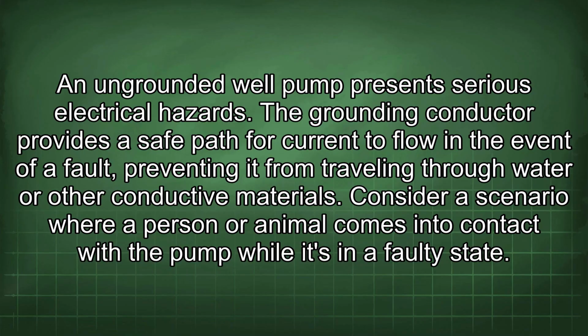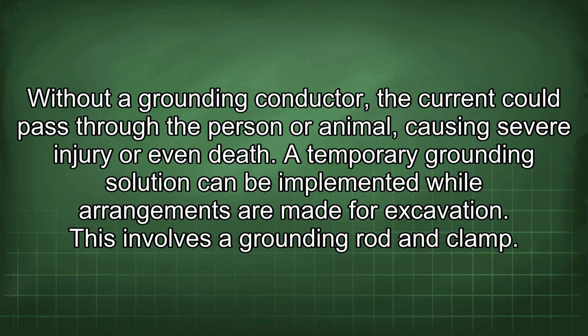An ungrounded well pump presents serious electrical hazards. The grounding conductor provides a safe path for current to flow in the event of a fault, preventing it from traveling through water or other conductive materials. Consider a scenario where a person or animal comes into contact with the pump while it's in a faulty state. Without a grounding conductor, the current could pass through the person or animal, causing severe injury or even death.